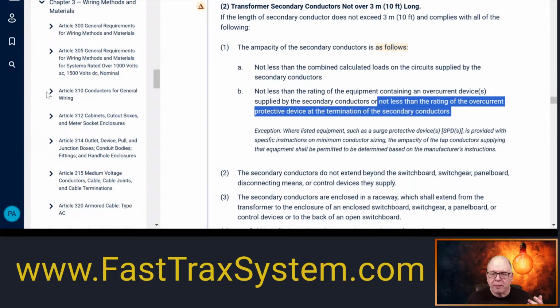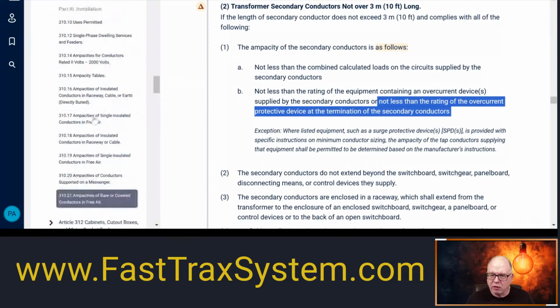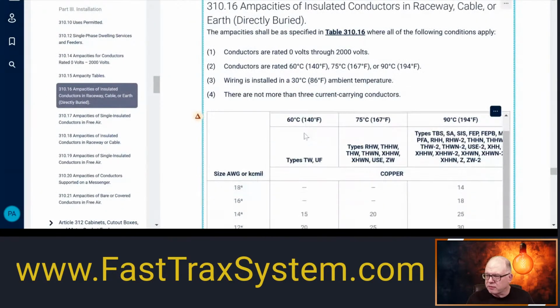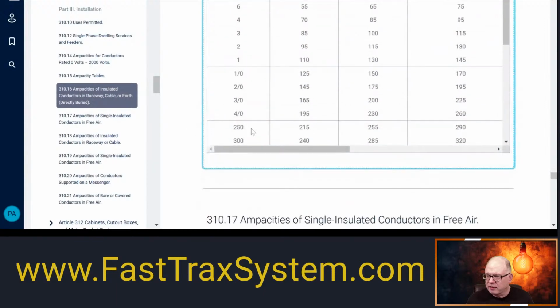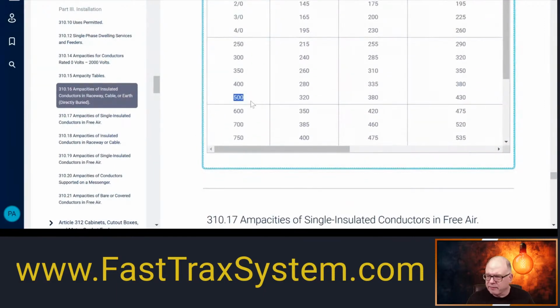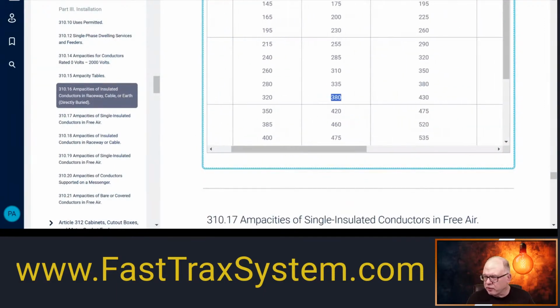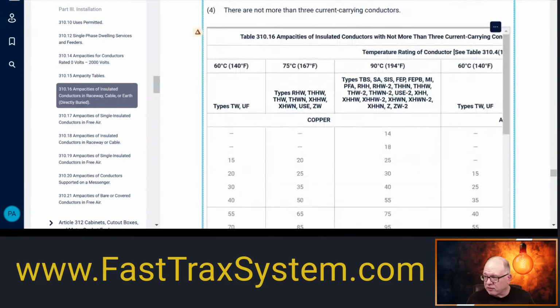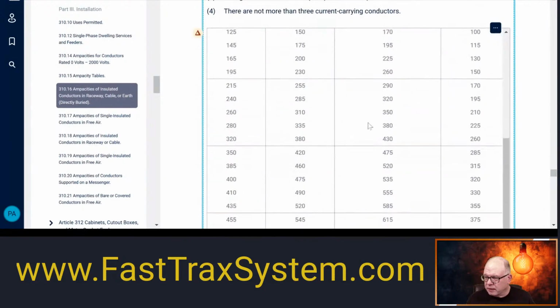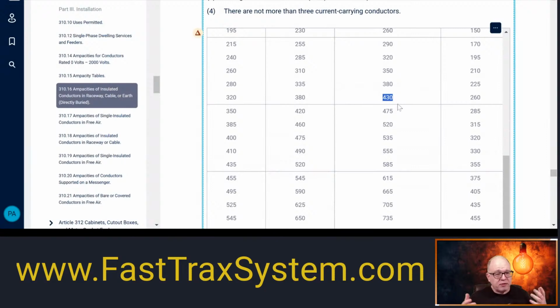And we always assume copper unless stated otherwise, right? So we'll go look at a 500 kcmil. We're at this table, so we're right here. Here's a 500 right here, and it looks like it's good for 380 amps. Again, people ask, I can't use this 90 unless I'm doing adjustments and corrections, or everything is rated 90. And chances are the lugs, probably in a transformer, may or may not be rated 90, but the ones at the breaker in the panelboard are probably not going to be rated 90. Okay, so we're going to be in the 75.